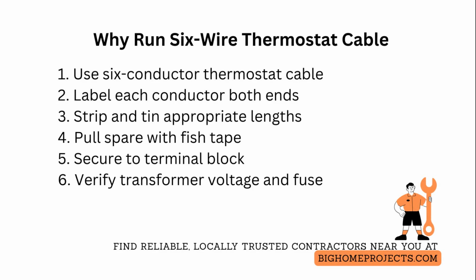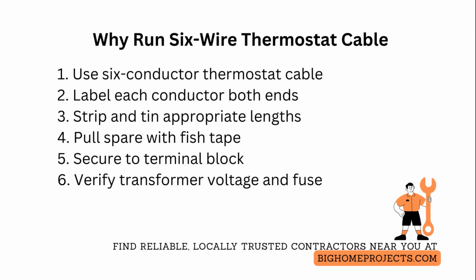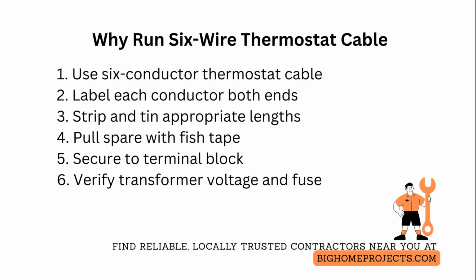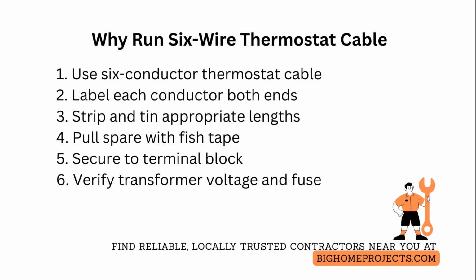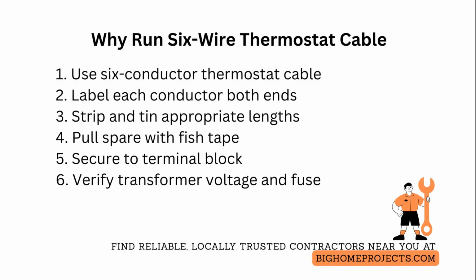Strip and tin only the insulation you need, and use consistent color-to-function mapping: common, heating call, cooling call, fan, and power or auxiliary. Then reserve the 6th conductor as a spare or for future smart thermostat features like a separate humidifier control or zoning sensor. When pulling through long runs, add lubricant and pull a fish tape in a second pass so you can replace the spare without opening walls.